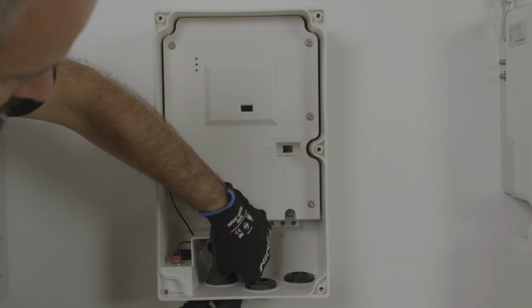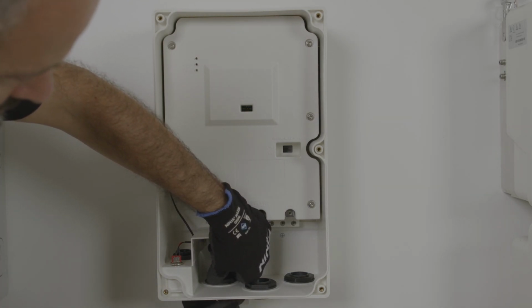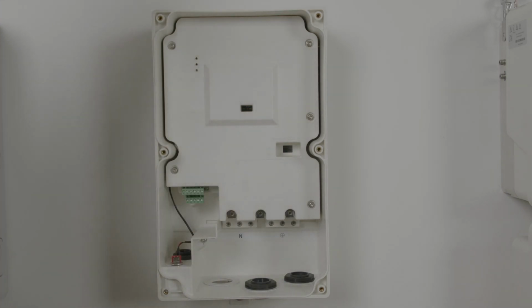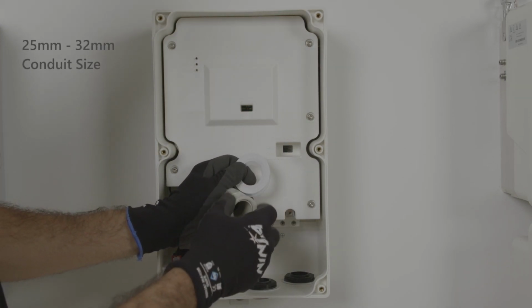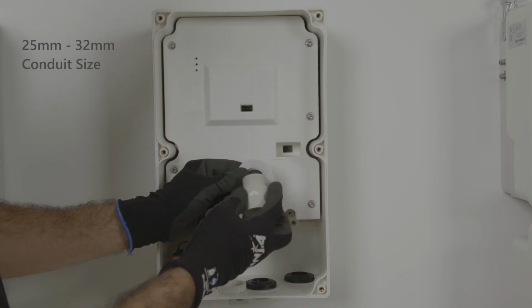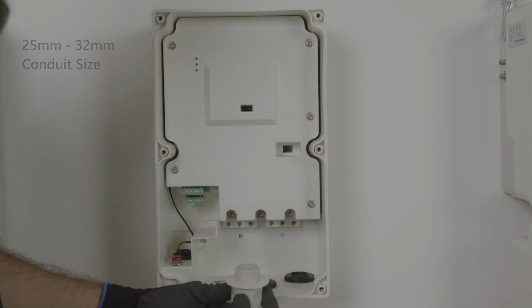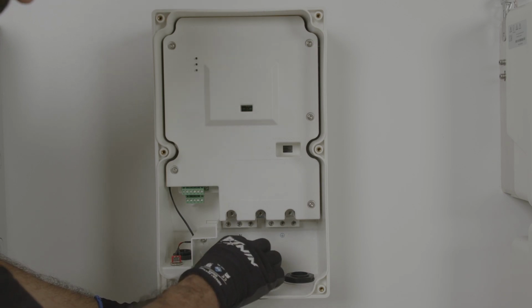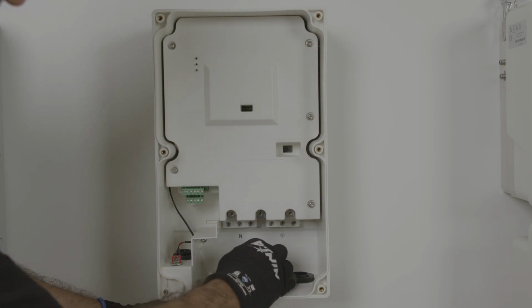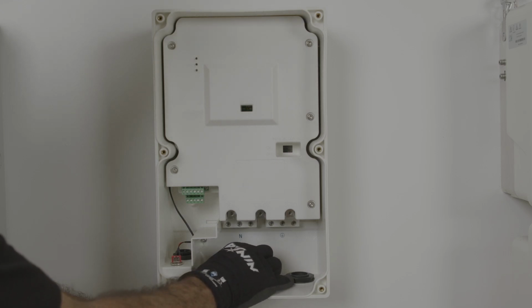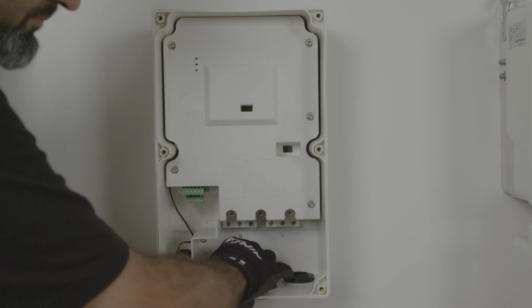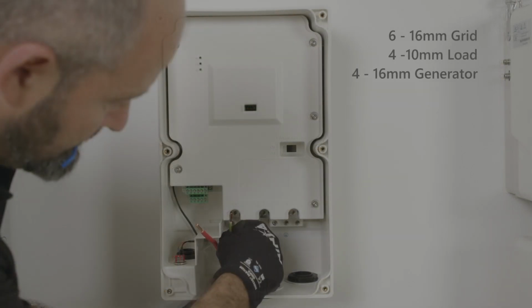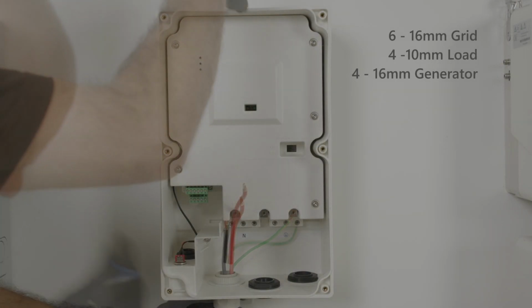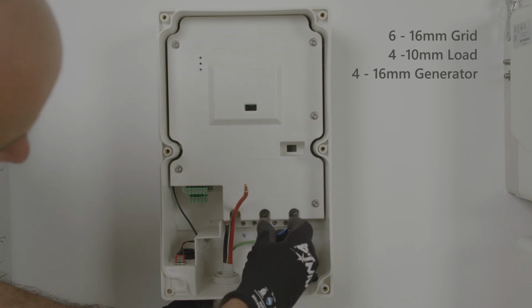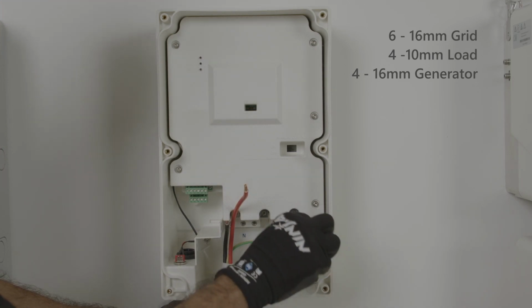The backup interface has provision for conduit entries from 25 to 32 mm. So for the AC connections from the grid, you can use between 6 to 16 mm² CSA cable, to the loads between 4 to 10, or if a generator has been connected, between 4 mm and 16 mm.